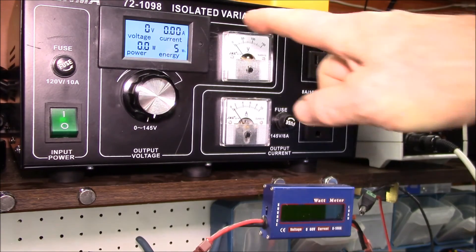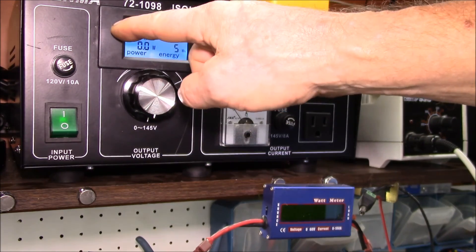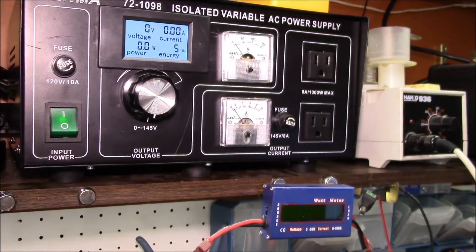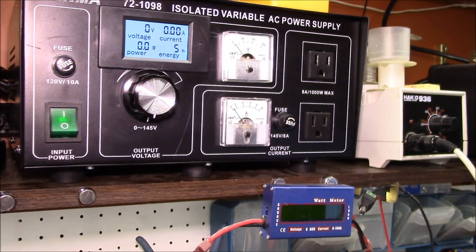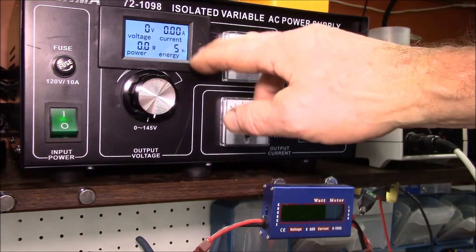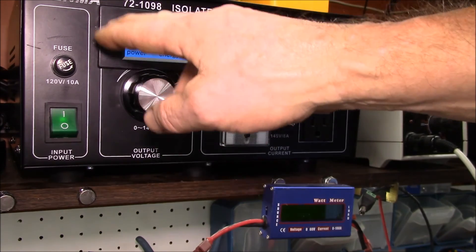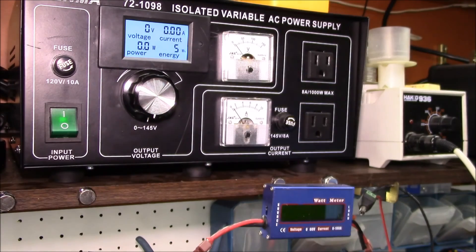The one thing you have to watch for is once you break that power connection inside the meter, you're now assuming there's a shared neutral connection, and you have to get that neutral connection hooked up properly. If there isn't a shared neutral, this won't work - you're going to have to power the meter off of the voltage you're sensing.